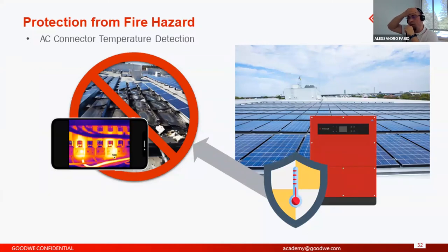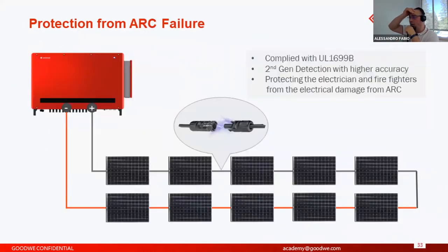We have also a protection inside for fire hazard protection, so AC connector temperature detection. This is a special option that we can put inside. With these options, you can measure the temperature inside, and you can detect also some problems, for example, when you have problems on the AC side connector or DC side connector. Also, arc fault protection is integrated inside. And if you have some problems inside, or you accidentally disconnect a DC side cable, for example, causing an arc, this protection can disconnect and protect the inverter automatically.